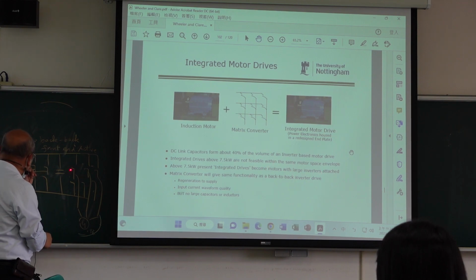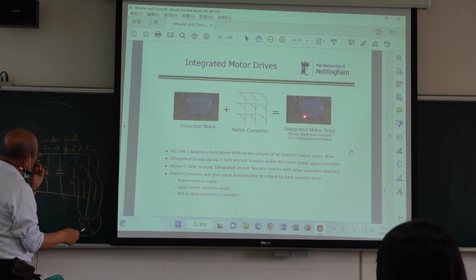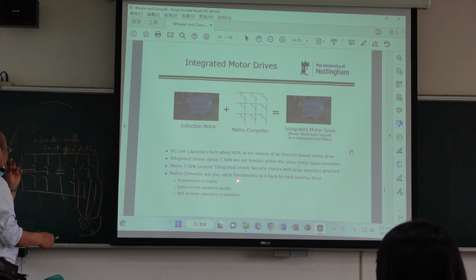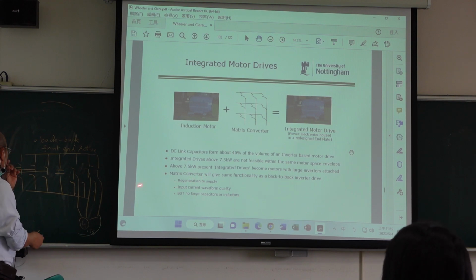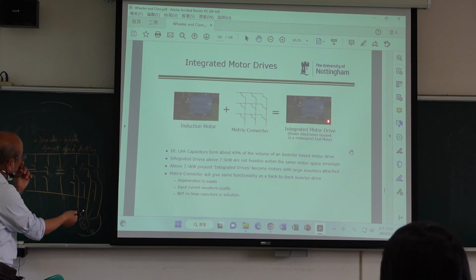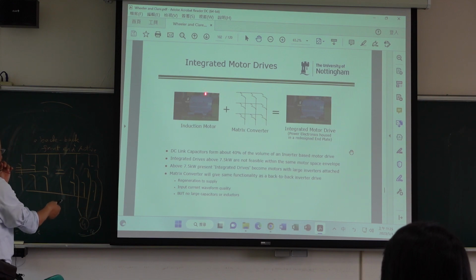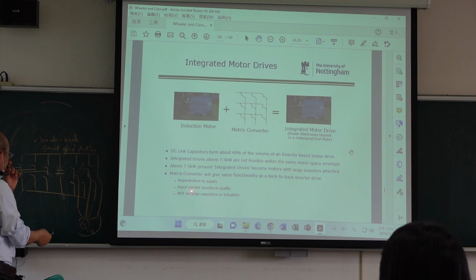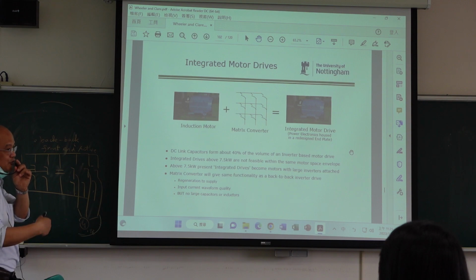However, a back-to-back inverter needs a huge capacitor. The matrix converter does not need a huge capacitor, and we can do regeneration, so energy can go back from the motor to the grid. The input current waveform is sinusoidal, and the input power factor is 1.0.